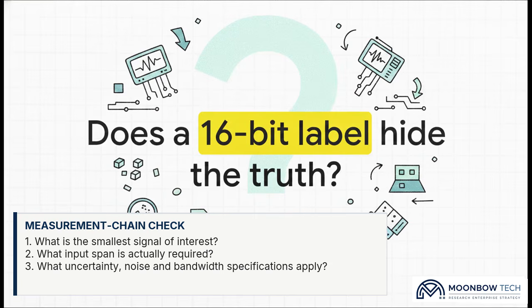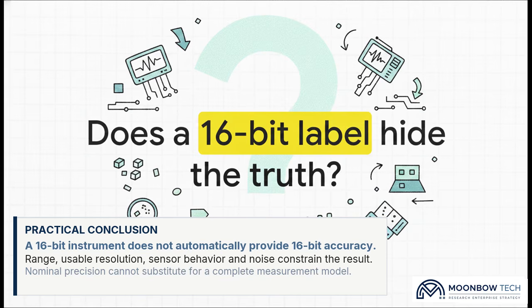A nominal 16-bit label sounds incredibly precise, but as we've just seen, it absolutely does not guarantee 16-bit accuracy. You cannot just combine these errors into a single magic accuracy number without a strictly defined statistical uncertainty model. So I'll leave you with this to think about as you head back to your lab benches. Does your 16-bit label hide the mathematical truth of your measurements? Audit your instrument chains, rigorously check your spans, and never take a bit depth specification at face value.